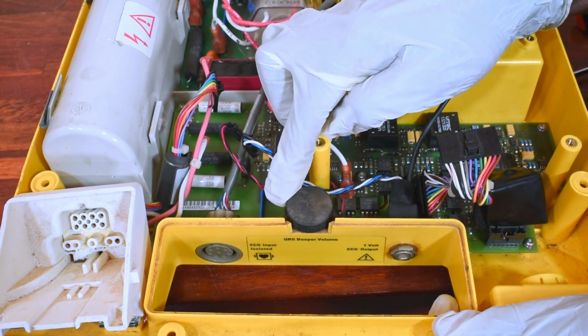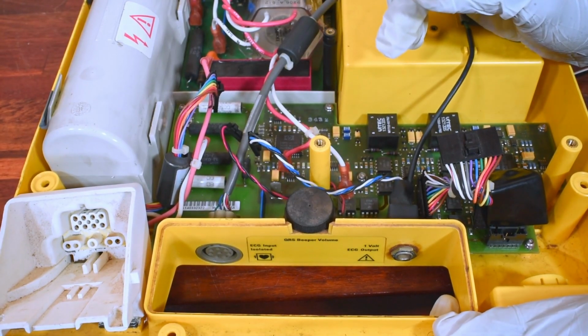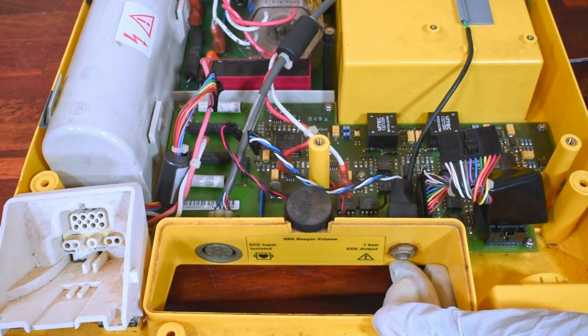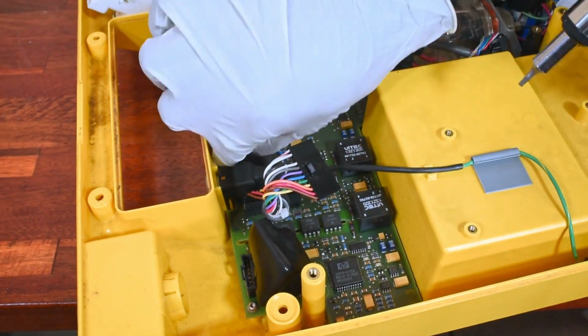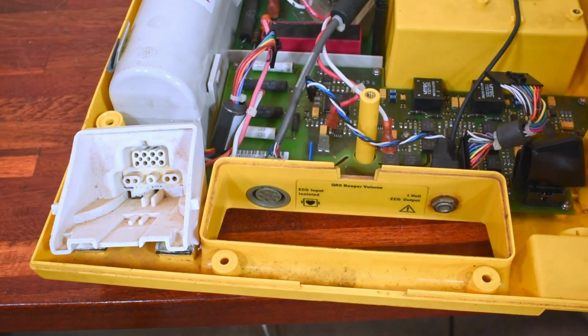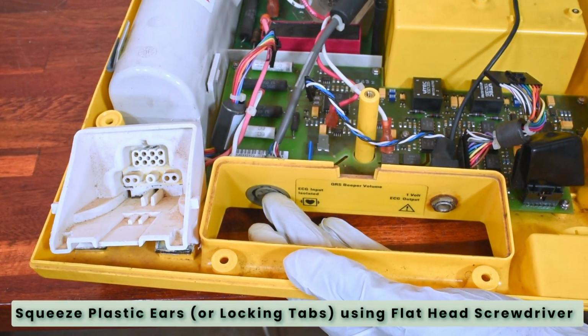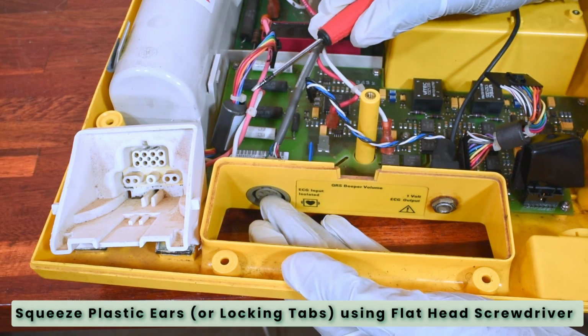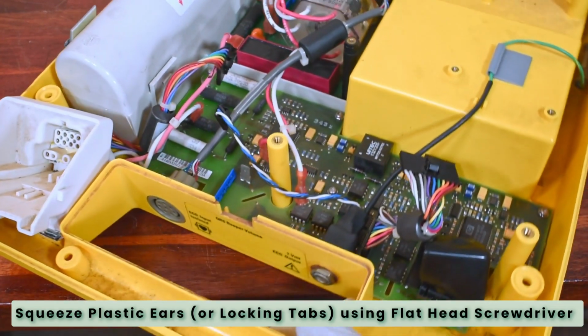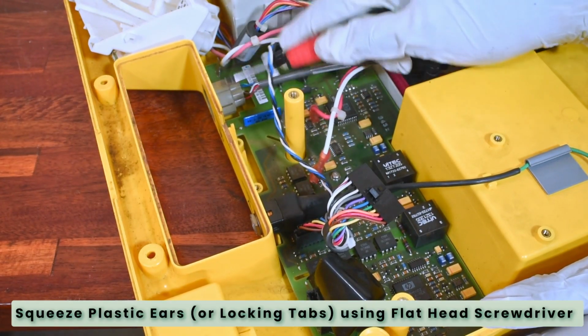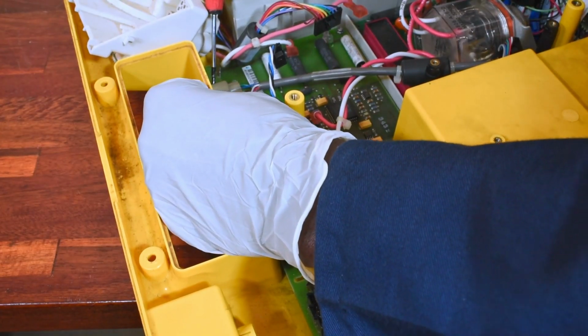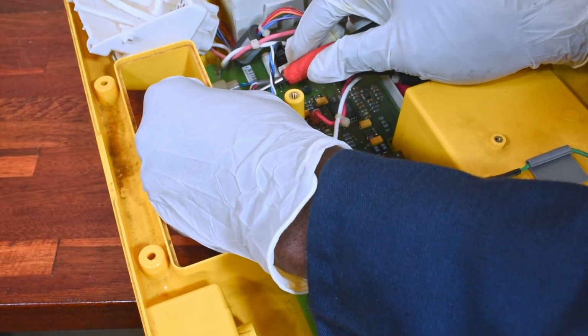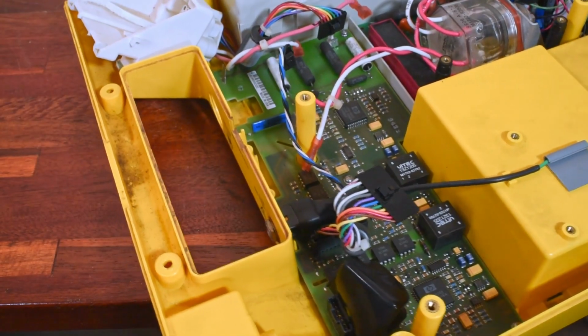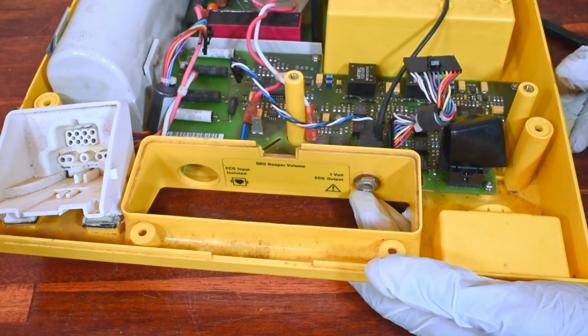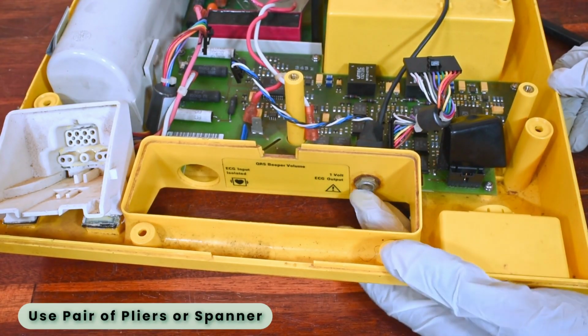Next, the QRS beeper volume control can be removed using a nut driver and a T10 Torx key. The ECG input connector can be removed by squeezing the plastic ears on the connector, after which the connector and the cable pull out to the front of the device. This one is the plastic ear, with the other one on the other side. The ECG output connector right here can be removed using a pair of pliers or a spanner.